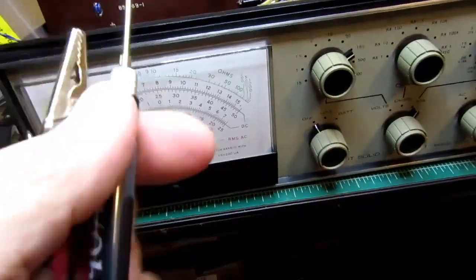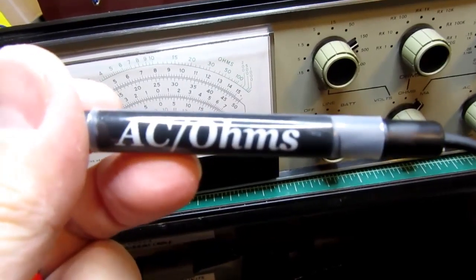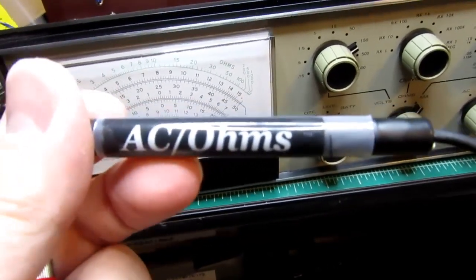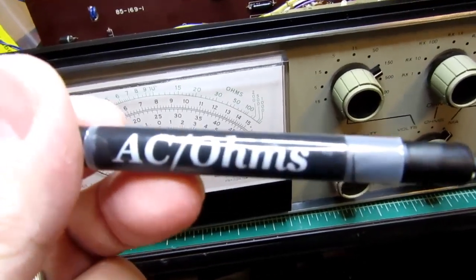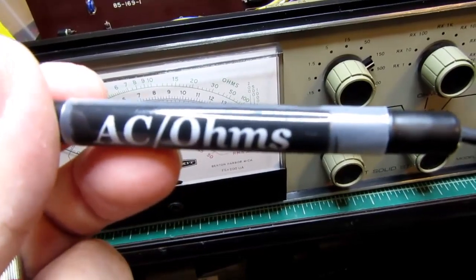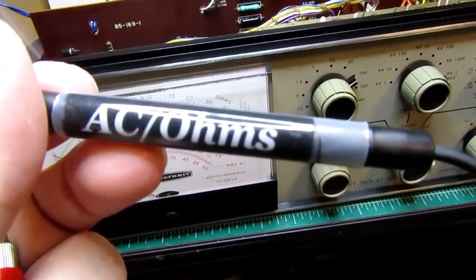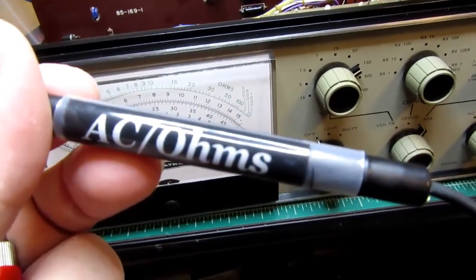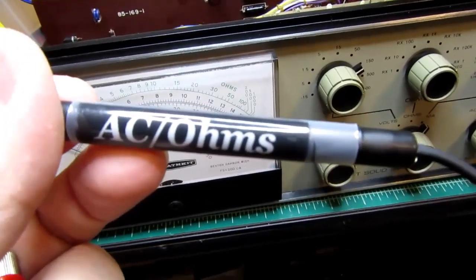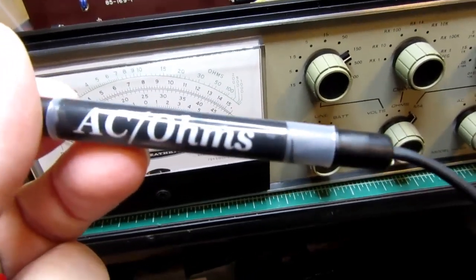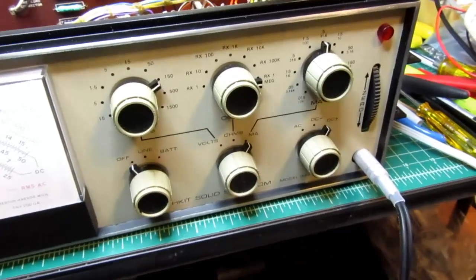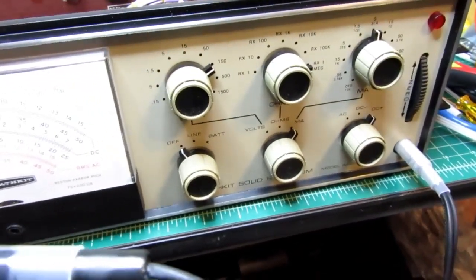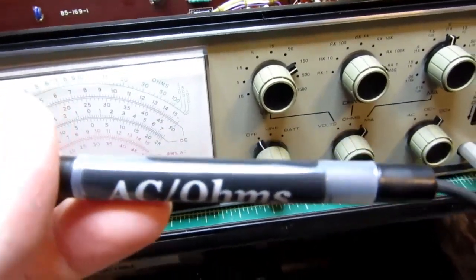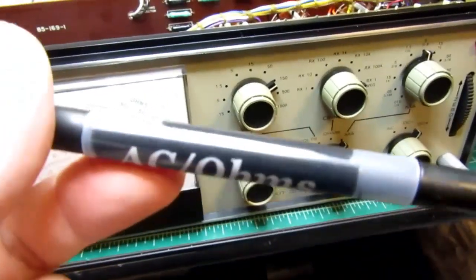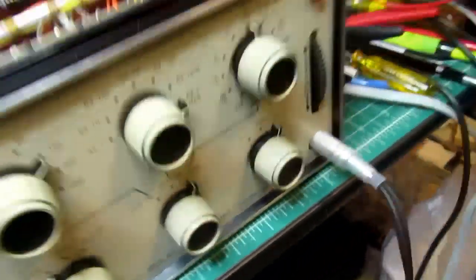And then another probe, which is usually labeled for AC volts and ohms, and that's based on the VTVMs, which don't have current function. They can't measure current. Very rarely do they do that. So they can measure ohms and AC and DC volts. And so the probe will be labeled AC/ohms, but in fact, if you do use it with an instrument such as the IM-25, which can measure current, milliamps, this is also the probe to use for that. So for every mode you use this probe, and that's the one without the resistor in it, except for DC volts where you have to have the resistor in it.